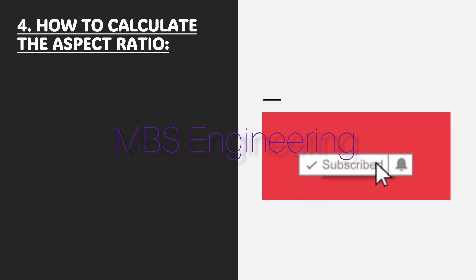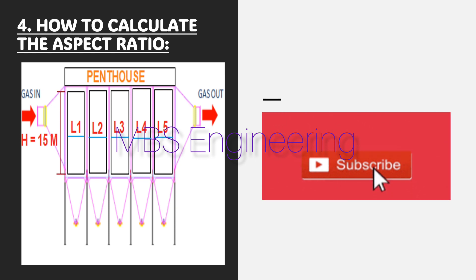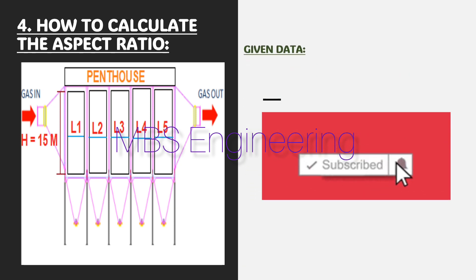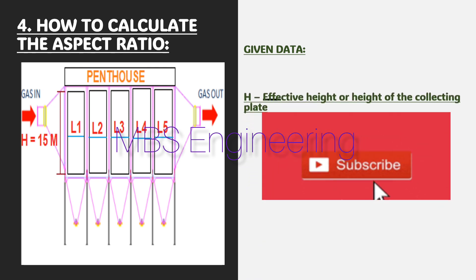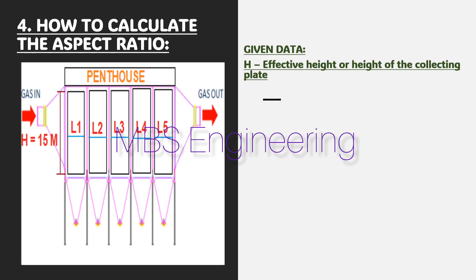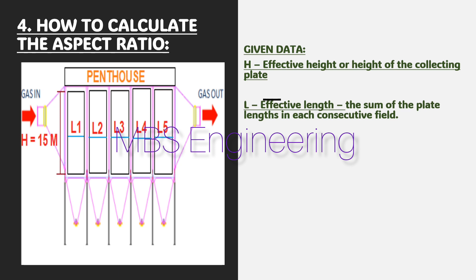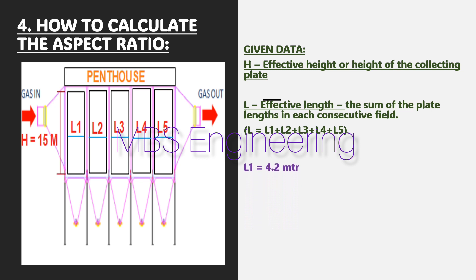Next, we are going to understand how to calculate the aspect ratio in the ESP. The aspect ratio equals effective length in meters divided by effective height in meters. H is the effective height or height of the collecting plate. L is the effective length — the sum of the plate lengths in each consecutive field. Please refer to the ESP schematic layout for better understanding — a 5 consecutive field ESP schematic layout is given.